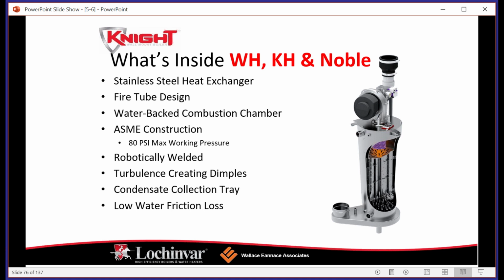Why do we want to create turbulence in the heat exchanger? Shouldn't we just blast the heat straight through and let it go on its way? The reason that we want to create that turbulence is to make sure that we get our maximum heat exchange, right? So it gives the flame a little more time to dwell in the heat exchanger and make sure that we're putting that heat into the water rather than the flue, okay? So again, one of the pieces of the puzzle that when you put them all together, you get this high efficiency, that AFUE that we were looking at. So again, this is a good example too.